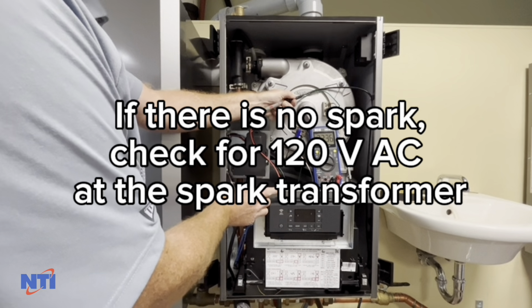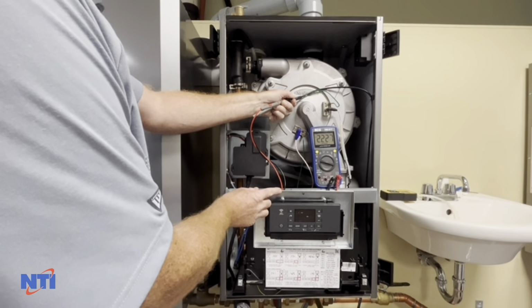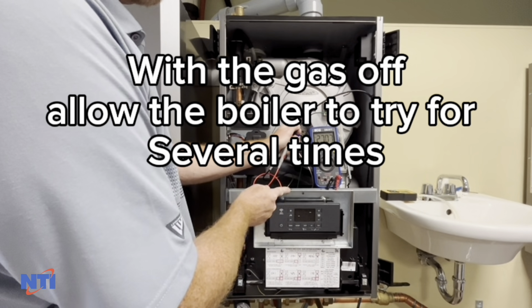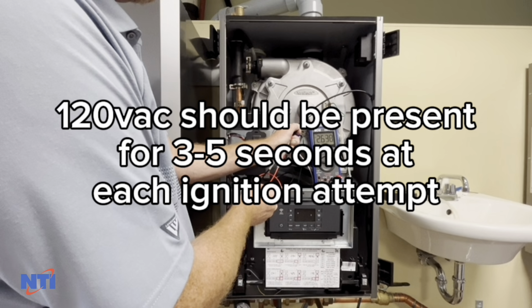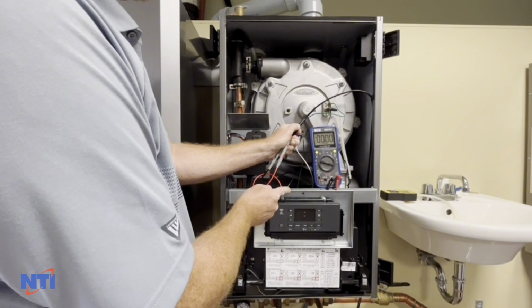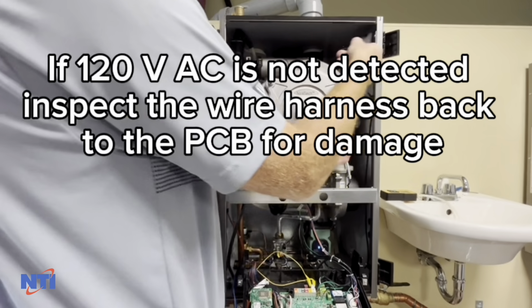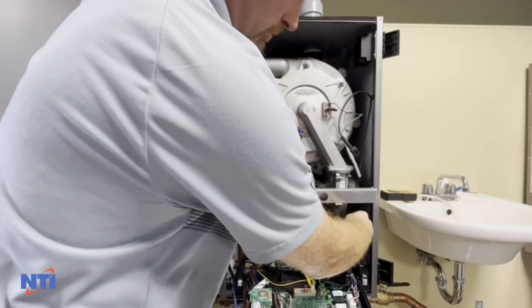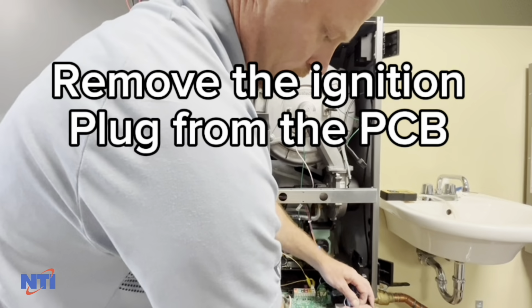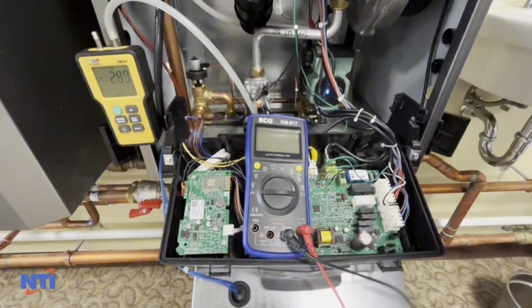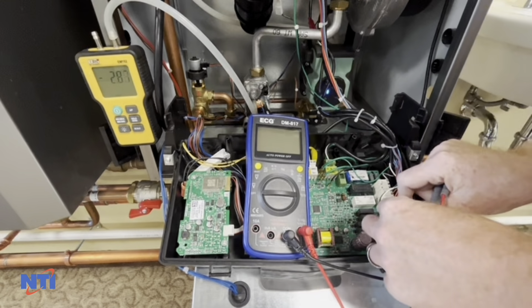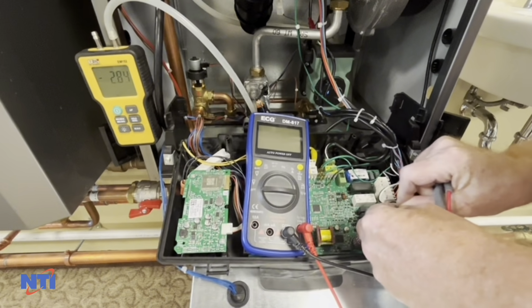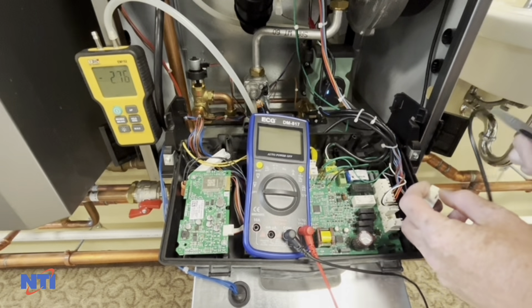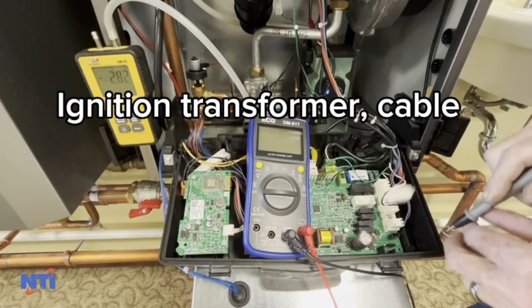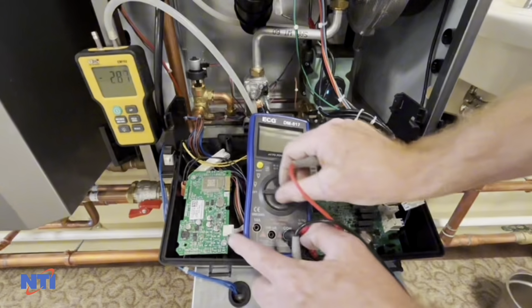If no spark is detected, we will need to check for 120 volts to the ignition transformer. Start by removing the 120 volt connection to the transformer. Cycle the boiler through several ignition attempts and test for 120 volts. If 120 volts is not seen, trace the cable back to the main PCB. Then test at the PCB across the two contacts for 120 volts. Ensure the boiler is actively calling for heat and attempting ignition when checking for power at the control board.